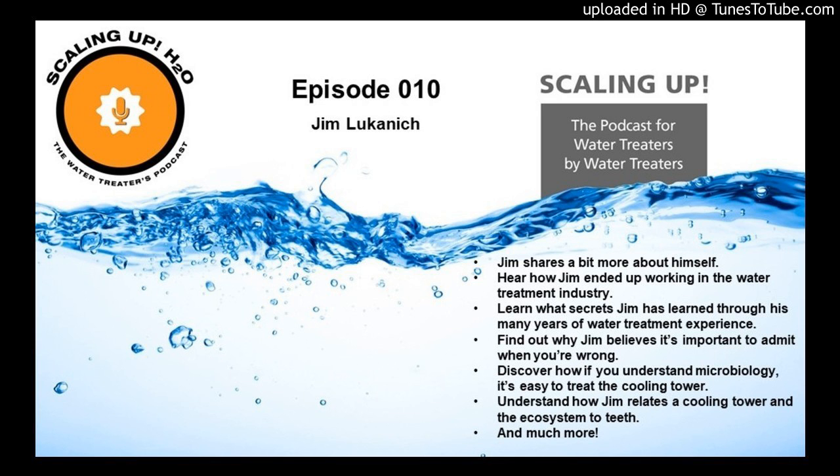However, if you are running, say, 100 ppb on your fluorometer and you add TTPC, it may drop that. There's going to be a dose response, but you may drop it down with the typical dose to 70. So if you're automatically controlling your PTSA level, you're going to feed more product. So you may be overfeeding product. Now, the good news about that is you can account for that and understand that you're slug dosing a biocide like that maybe once or twice a week. So that effect would probably last over a period of hours rather than all the time. So it may be less concerning than it sounds, but you'll need to be aware of it so you can make adjustments in your program for when you're going to feed it.